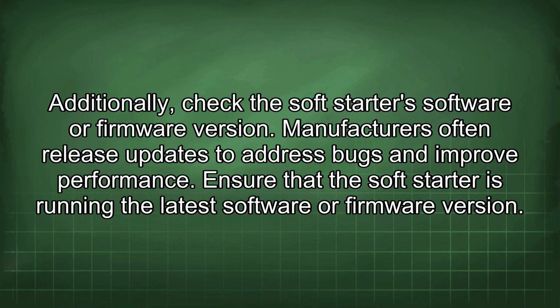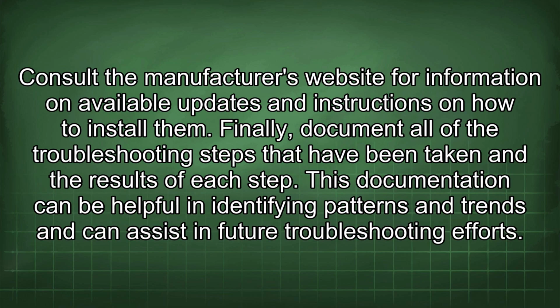Additionally, check the soft starter software or firmware version. Manufacturers often release updates to address bugs and improve performance. Ensure that the soft starter is running the latest software or firmware version. Consult the manufacturer's website for information on available updates and instructions on how to install them.